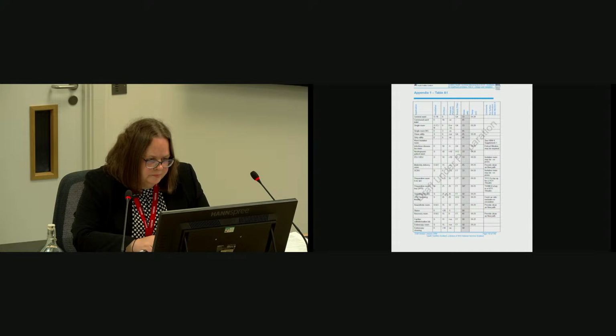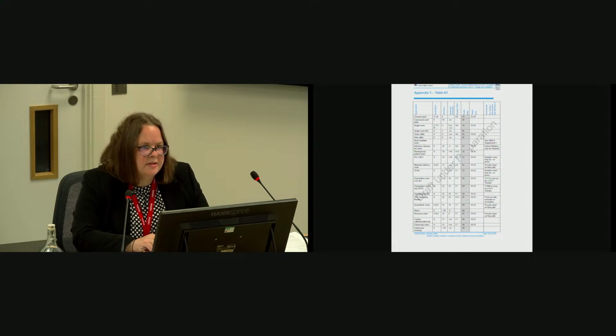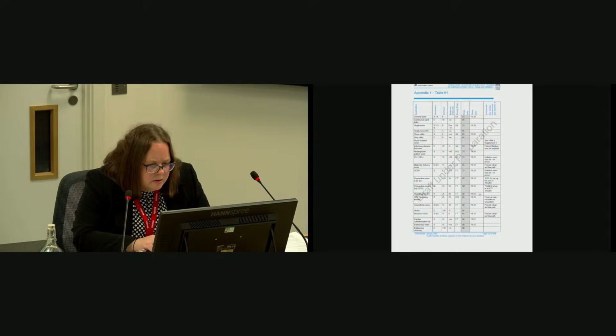Yes. And then you have an F7 filter. Now, is that what we've been talking about as a HEPA filter, or is it just more conventional? No, that's not the same specification as a HEPA filter - that is less efficient than a HEPA filter. And then we have a temperature range of 18 to 25.